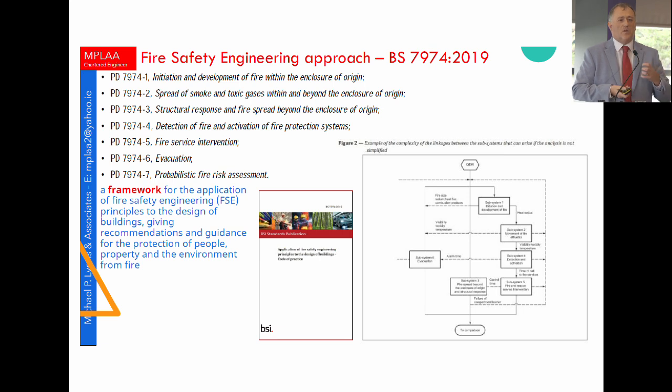I think there's a growing recognition that there needs to be some kind of an evacuation plan considered by people as well, particularly by fire safety consultants. And the more complicated buildings become, the higher they become, the way in which people will evacuate is a really important part of the fire safety strategy. And it can't be taken for granted in a performance-based design. So you actually have to deal with it as part of one of the subsystems.